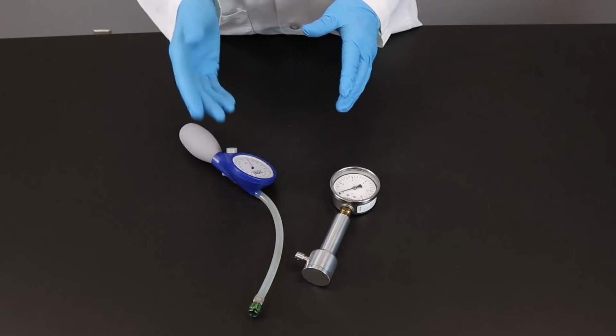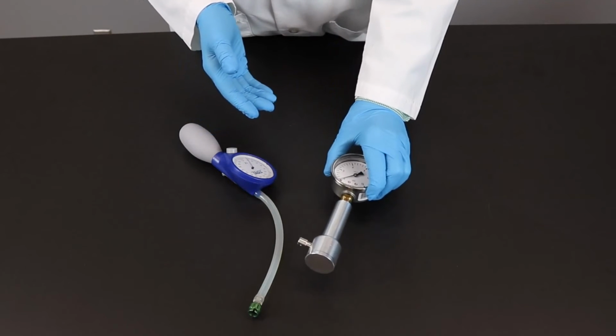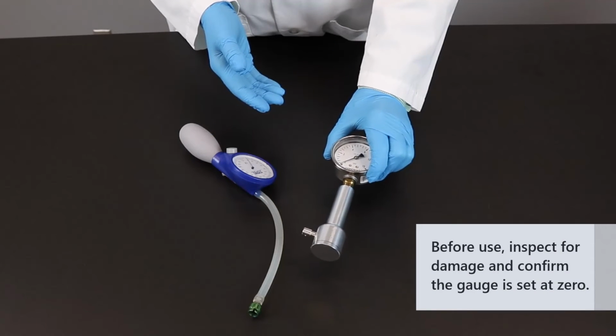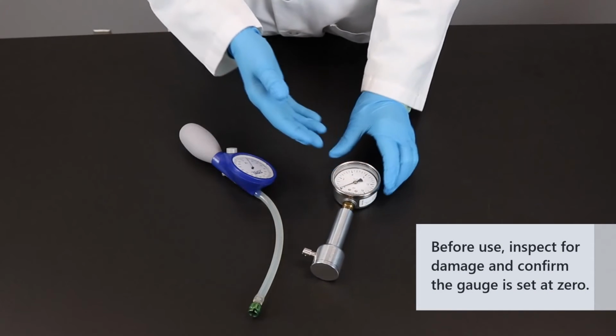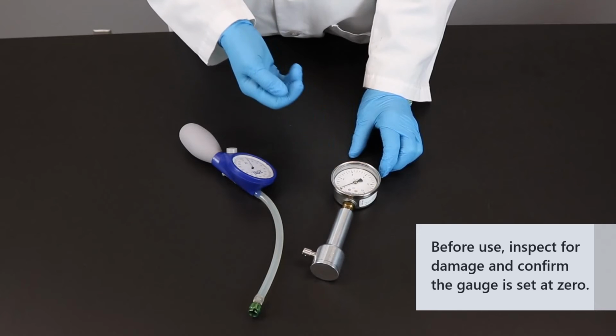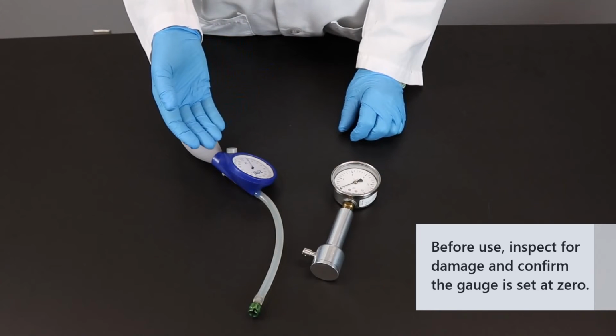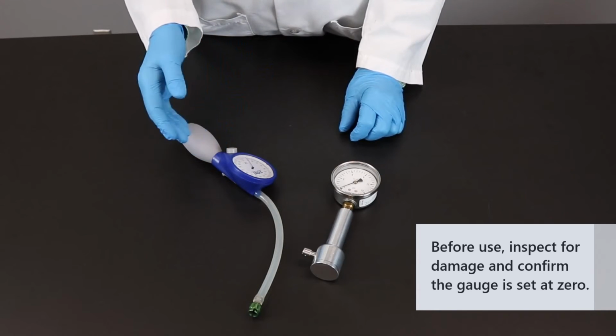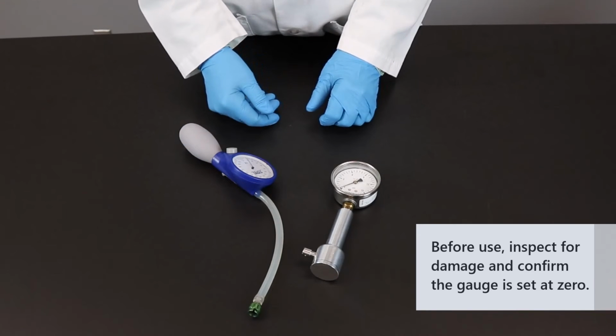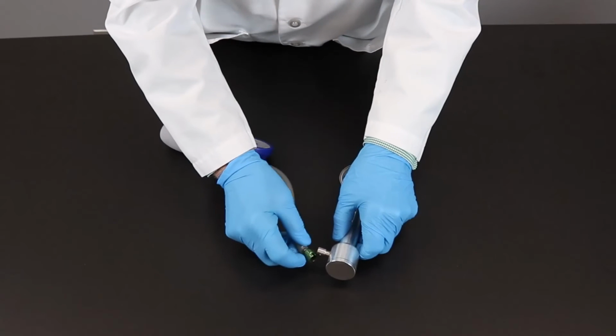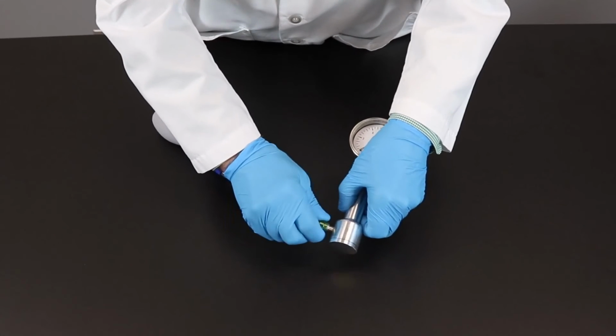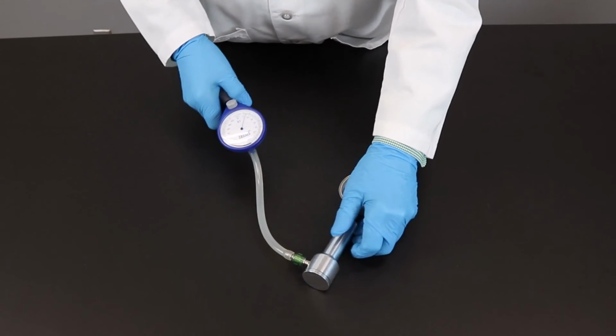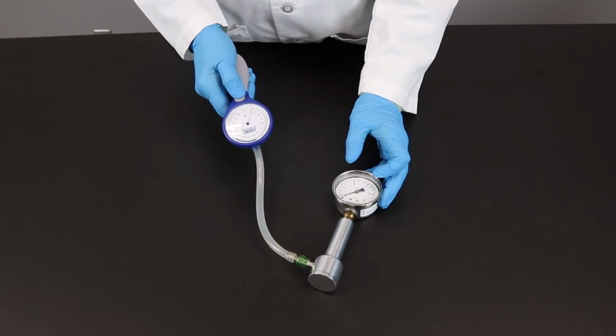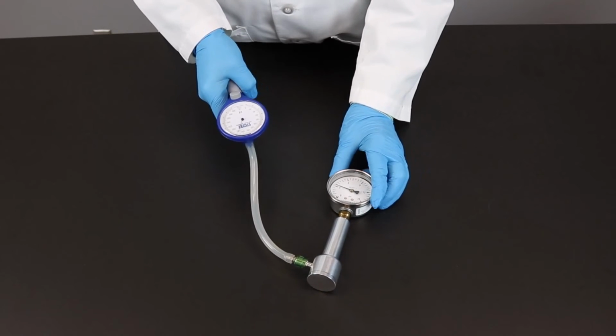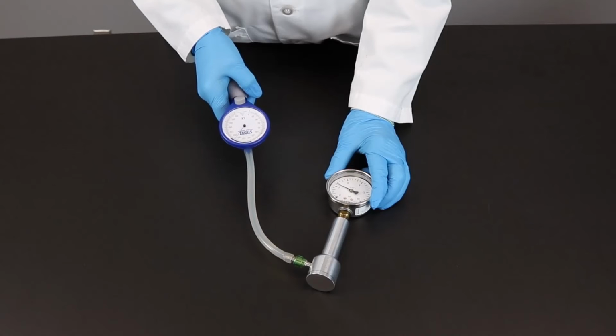So what we're going to do is inspect the leak tester for any visible damage before we use it. We're going to make sure that the gauge is set at 0. And then we're going to do the same for the leak tester to make sure that we're not seeing any visible damage that could affect the results. To perform the test, we're going to connect the two together. We're going to inflate the leak tester gauge into the range that you normally would for a test.